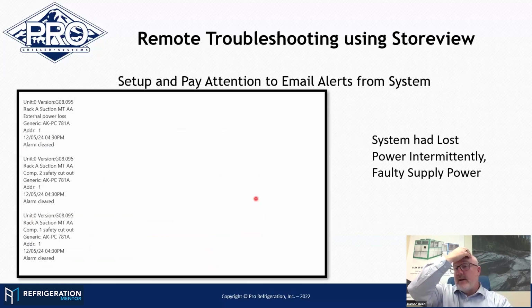Yeah. Setting up the email alerts. That's another thing that is overlooked. It's not done often enough, and then it can be ignored a lot of the time. It's easy to dump emails into a junk folder or clutter. But here was an example of an email that came through from a system where we had two compressors both trip on safety cutout, but you notice at the top, an external power loss is identified.